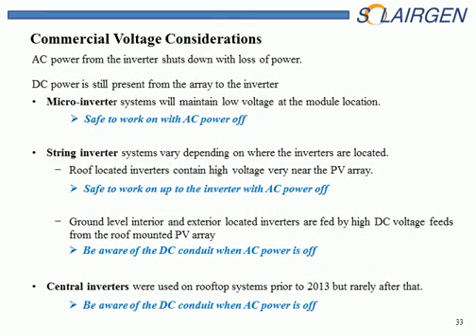Let's review the commercial voltage considerations. Microinverters, we know that it's isolated, to the module. The string inverter is usually located close to where the PV array is. Not necessarily, but usually it is. So if you can observe that, you see the inverters located close to the PV array, then all the DC is isolated at that point. If you see a ground-mounted inverter, then you know that there's DC feeding down to it. So a big central inverter, of course, means that there's very high voltage, high current coming through those conduits. So try to avoid those if you can in any way.